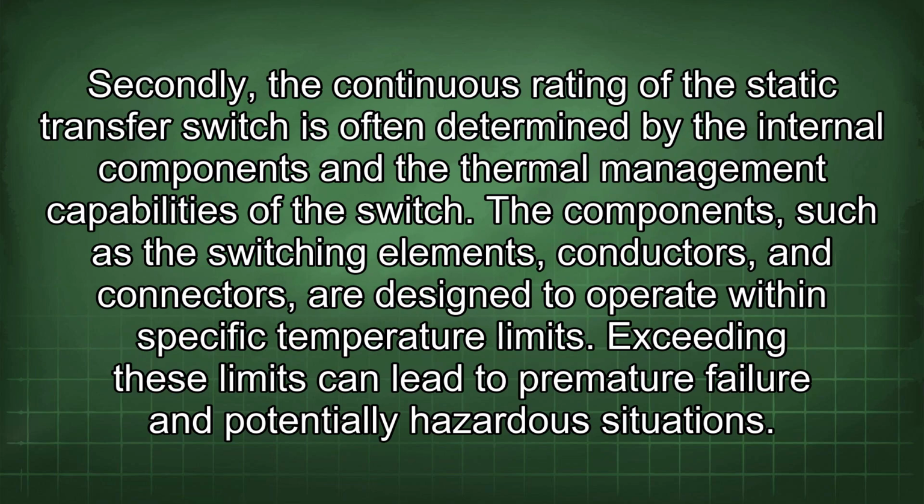Secondly, the continuous rating of the static transfer switch is often determined by the internal components and the thermal management capabilities of the switch. The components, such as the switching elements, conductors, and connectors, are designed to operate within specific temperature limits. Exceeding these limits can lead to premature failure and potentially hazardous situations.